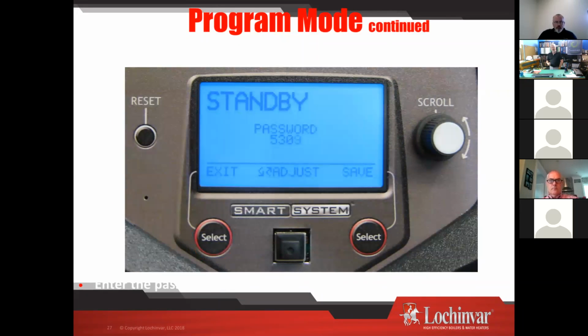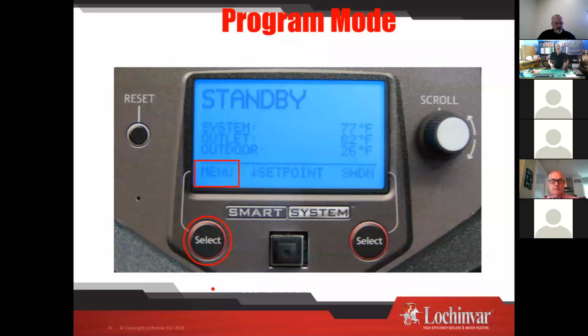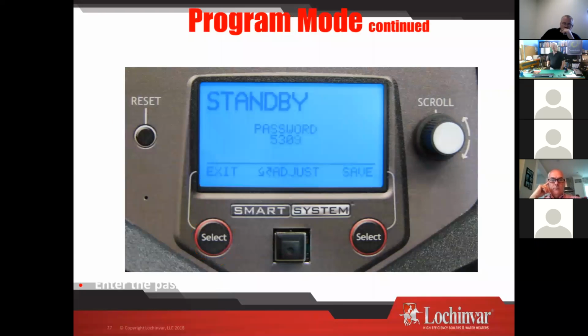Password. Password is 5309. That is every Lochinvar boiler out there uses 5309. And yes, that is from the Tommy Two-Tone song, and that is Jenny's phone number. To get to where we enter the password, the menu button, push and hold that. Now again, push and hold it for 5 seconds. We take a few calls every year, somebody saying, hey, it's not working, I'm holding this for 5 seconds. So if you then say to them, hey, hold it until it says enter password, they're much more successful. So hold it until it says enter password. Like I said, it's a southern boiler, and things move a lot different in the south than they do up here right now. All right, so once we get that done, use our scroll knob to set it, save it, and now it'll take us into the programming.